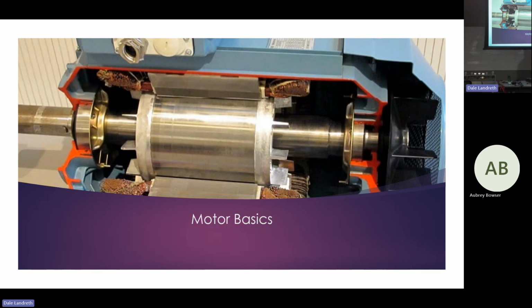The rule I've always been told for Meg testing motors: if it's a 460 volt motor, you test it at 1,000. If it's 120, you test it at 250. You test it at twice its rated voltage. So if I have a medium voltage 4160 motor, I've got to take it to 10,000 volts. Does that make sense? And I don't have a 10,000 volt Megger.